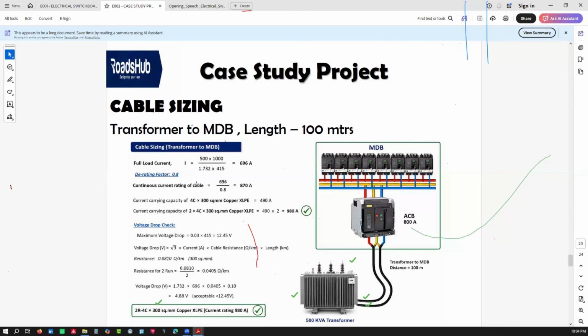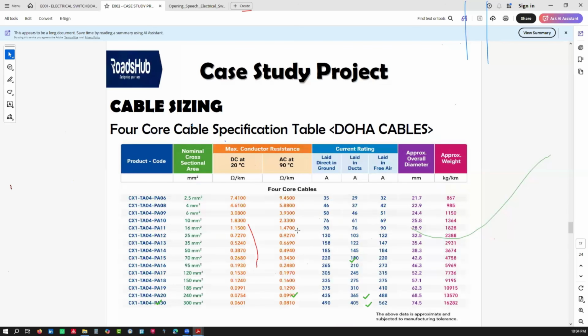The same way we've done the calculation for the cable between the SMDBs and the DBs in the house. And then you get what we call a continuous current rating of the cable. So you have 696, but you divide by 0.8, that goes to 870 amps. For you to get a cable that can handle 870 for this cable catalog, it's not possible, because look at the highest current if I'm laying the cable underground, because from the transformer to the main DB, we can lay cables underground. So I want you to check the last digit. We have 300 mm squared. For 300 mm squared, the current when you lay the cable in the ground is 490.